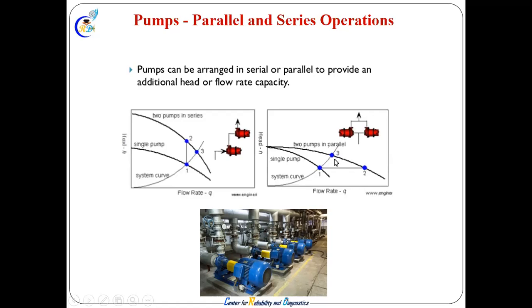You will get, because you have to encounter the system site condition, the system curve. So we are not doing like this. The system curve is the same for the particular installation, but I have put two pumps. Okay, right? So with two pumps, the intention is double flow, but in practice you never get double flow.